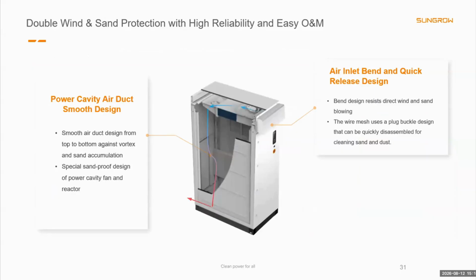For desert conditions like maybe the Middle East, 1+X uses a smooth air duct design to reduce sand accumulation. The air inlet also helps resist direct wind and sand impact. The mesh can be removed for cleaning. These features reduce maintenance work while maintaining cooling performance.